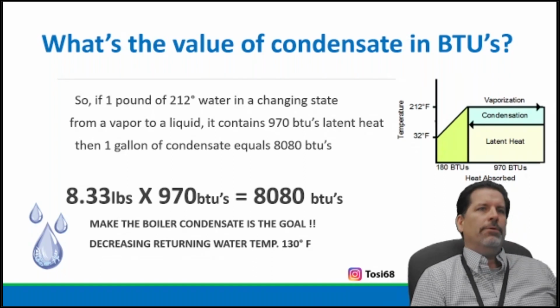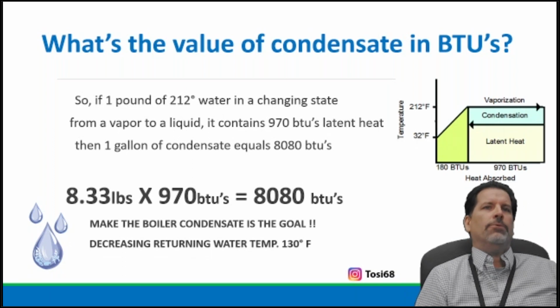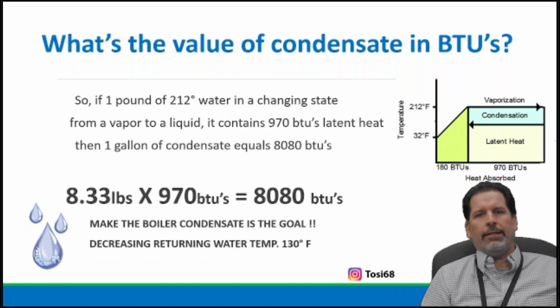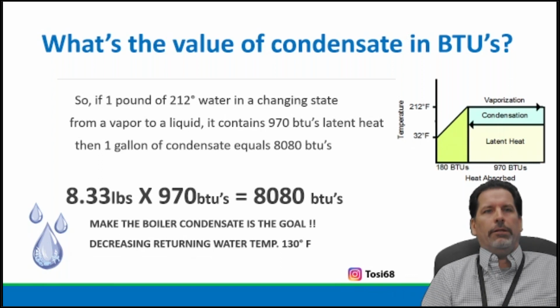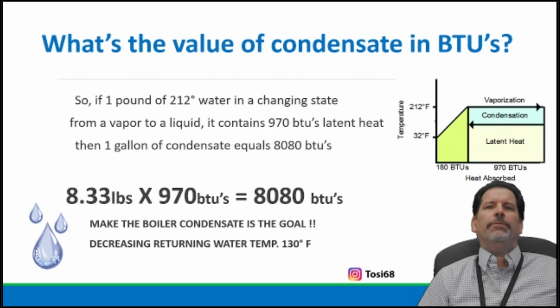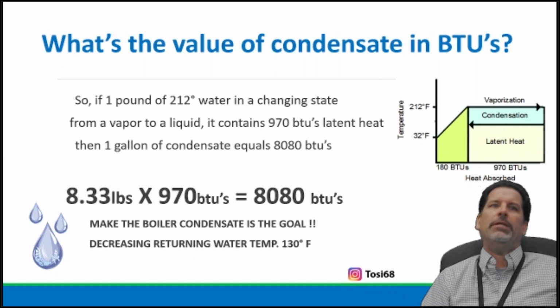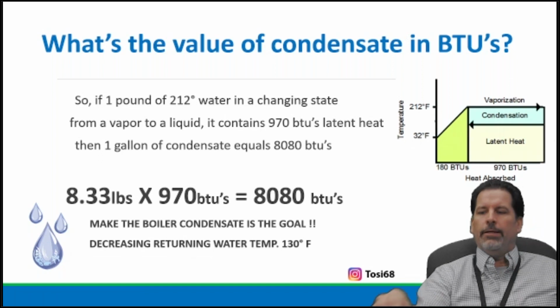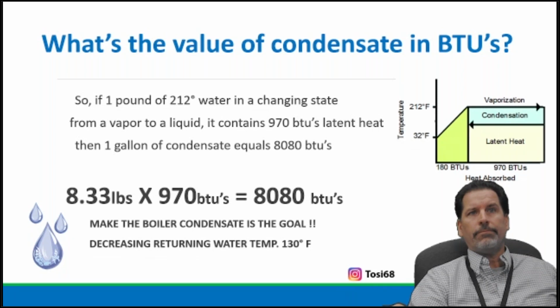Again, a gallon of water is 8.33 pounds, right? One gallon of water, times 970, equals 8,080 BTUs. If you could honestly collect your condensate and measure how much you reclaimed after collapsing vapor to a liquid, you can derive the BTUs that you've reclaimed, that you didn't lose, that you put back into the system, right? Using less fuel to heat the space, because this is what we're all engineered around. The little upper right diagram is showing you from 32 to 212 now, right? Before we vaporize, 212 liquid, 212 vapor, or steam, I guess, right? When we change that state from vapor back to a liquid, that's when it releases the 970 BTUs. That 970 now goes back into the corrosion-resistant stainless steel heat exchanger. Right there. That's what it does.